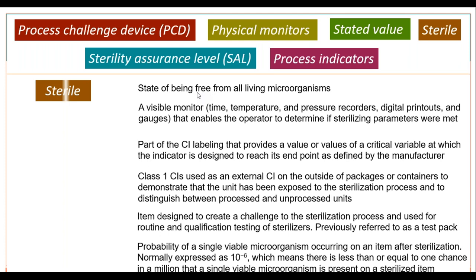The state of being free from all living organisms is sterile. Another definition they may bring up is a numeric value: 10 to the negative 6 would be considered sterile — meaning there is less than or equal to one chance in a million that a single viable organism is present on a sterilized item. That's our sterility assurance level.